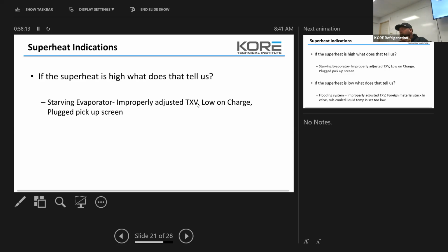Improperly adjusted TXV. What I will tell you about adjusting TXVs is a lot of guys do it differently. I always start at factory setting. I don't want to try to go where I think it started from, so I'll wind it in. The problem with winding in a TXV is if you go too fast and too hard, you'll over torque it. So go in slowly, back it out 3 full turns, and start from there. That's where factory setting is on a Sporlan. Then start adjusting superheat from there.